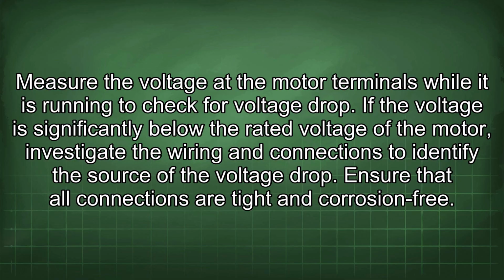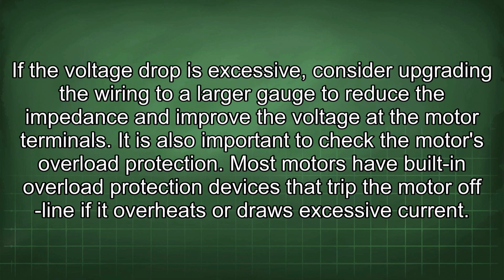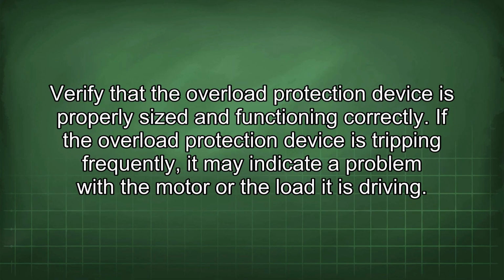Ensure that all connections are tight and corrosion-free. If the voltage drop is excessive, consider upgrading the wiring to a larger gauge to reduce the impedance and improve the voltage at the motor terminals. It is also important to check the motor's overload protection. Most motors have built-in overload protection devices that trip the motor offline if it overheats or draws excessive current. Verify that the overload protection device is properly sized and functioning correctly. If the overload protection device is tripping frequently, it may indicate a problem with the motor or the load it is driving.